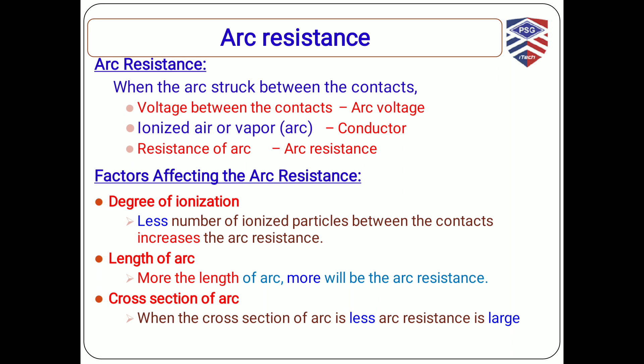There are different factors that affect the arc resistance. The arc resistance of the circuit breaker can be affected by the degree of ionization, the length of the arc, or the cross section of the arc. If we have fewer ionized particles between the contacts, the arc resistance would increase. By lengthening the arc, we can increase the arc resistance, as well as by decreasing the cross section of the arc. These are the different factors that affect the arc resistance.